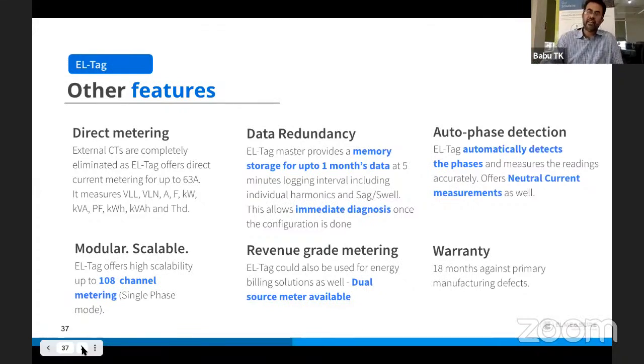You have another variant, multiple variants in this. We offer up to 63 amps in this particular one, and with a limit you can only use a 10 mm square wire. So 50 amps with an overload of 63 is perfectly all right, but not 63 with an overload beyond that, because you can only connect a 10 mm square wire through this. So you have 50 amps going up to 63 amps maximum, plus a 32 amps and a 5 amps version.